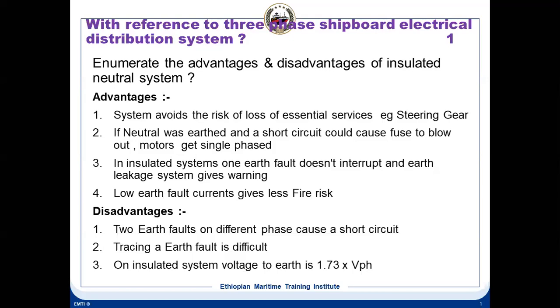Second, the disadvantage is that if one more earth fault comes on a different phase, it can become a short circuit, and then it will trip. Tracing an earth fault is difficult in neutral insulated systems. And in an insulated system, voltage to earth is √3 times the phase voltage. Okay, because phase voltage is line voltage divided by √3.